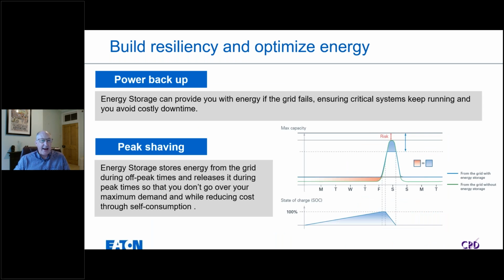Next one to mention is backup power. I think that's fairly self-explanatory. Effectively, you can use your battery to provide power to critical systems during a power outage. Next one, I should have said on the previous slide, actually, that integration of solar PV particularly is the number one driver for installing battery energy storage systems in the built environment. Number two is peak shaving. So this is where we have an increasing building demand that would require us to otherwise upgrade our building supply capacity.